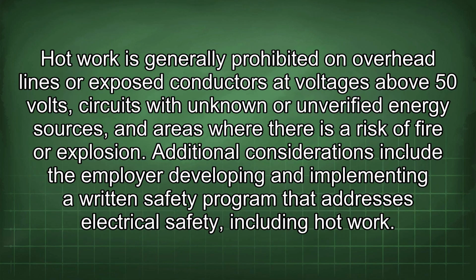Hot work is generally prohibited on overhead lines or exposed conductors of voltages above 50 volts, circuits with unknown or unverified energy sources, and areas where there is a risk of fire or explosion.